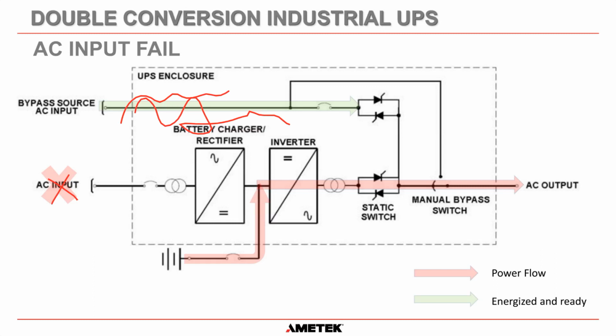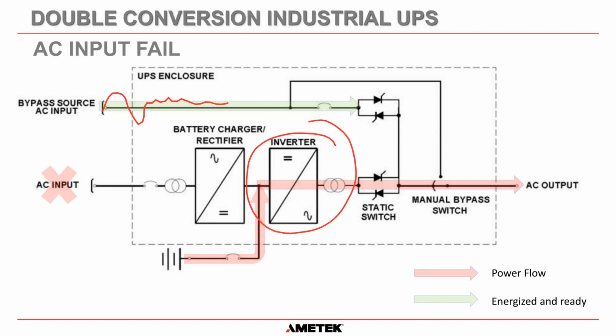So we don't want to transfer to bypass in that circumstance, because it doesn't matter how unstable the bypass is. Our inverter doesn't care about that. It's putting out a beautiful sine wave at 60 hertz, unaffected by what's going on in your plant. And we can guarantee that the power going out to your load is regulated and exactly what your load circuits need. Okay. So that is why we don't transfer to bypass. We stay on inverter. The UPS does everything it can to try and stay on inverter as much as it possibly can.